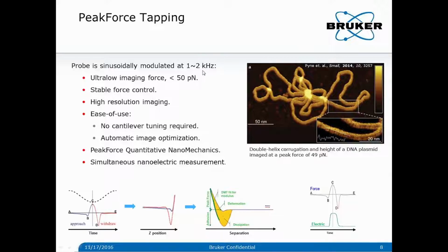Because of this tapping mechanism, it has many advantages. For example, it allows a stable and ultra-low imaging force, which benefits high-resolution imaging. It also makes AFM very user-friendly. For example, no cantilever tuning is required as it doesn't rely on mechanical resonance, and this is very convenient for liquid imaging. As you know, a lot of in situ battery research is in liquid. It also has a function called automatic image optimization, which really helps new AFM users a lot because it frees them from the tedious effort of feedback parameter adjustment.